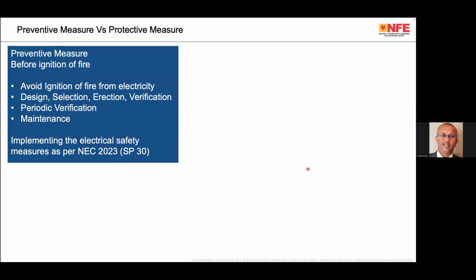It depends on the design, selection, erection, and verification of electrical installation, periodic verification, maintenance. These are the subjects which we need to focus on when we talk about preventive measures. All these subjects are explained. The preventive measures of protecting electrical installation from a thermal effect is explained in NEC or IS 732. Please note that the word used is thermal effect. The meaning is, under normal operating condition, electricity or a current using equipment or the electrical installation shall not produce a temperature which is more than the withstanding capacity of the equipment or more than the capacity of the environment.